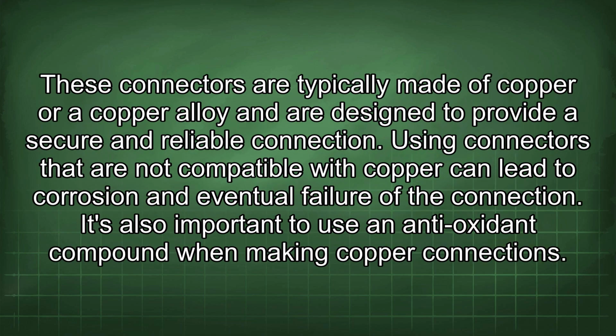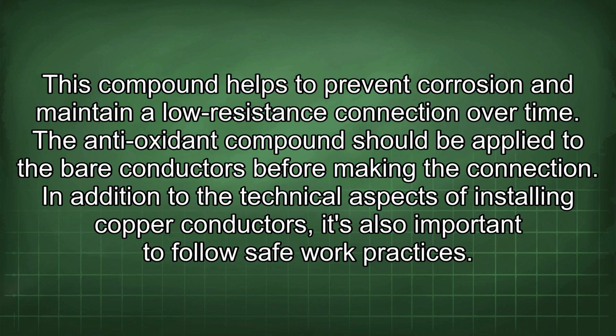When working with copper conductors, it's important to use connectors that are specifically designed for use with copper. These connectors are typically made of copper or a copper alloy and are designed to provide a secure and reliable connection. Using connectors that are not compatible with copper can lead to corrosion and eventual failure of the connection. It's also important to use an antioxidant compound when making copper connections. This compound helps to prevent corrosion and maintain a low resistance connection over time. The antioxidant compound should be applied to the bare conductors before making the connection.